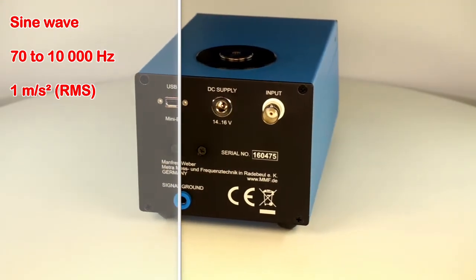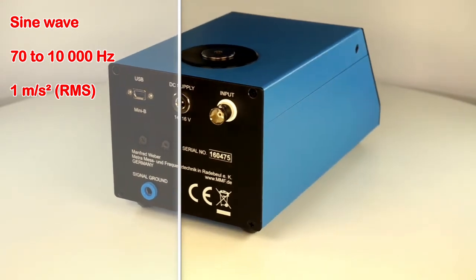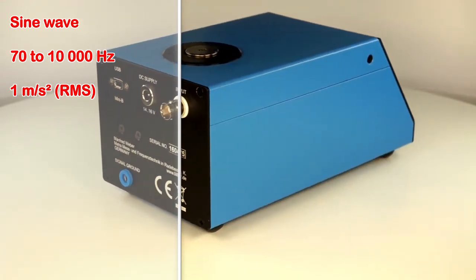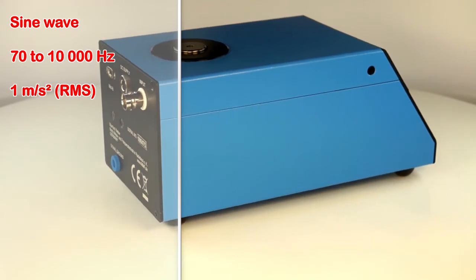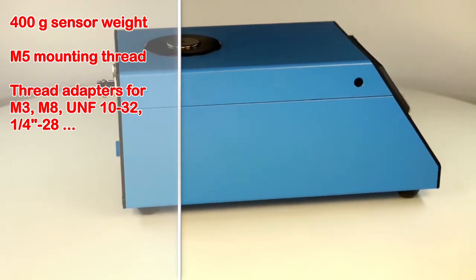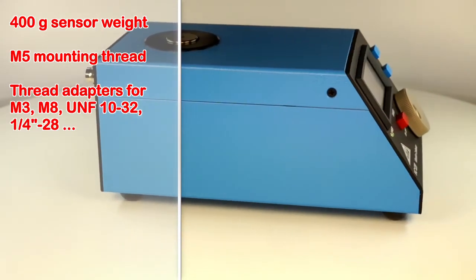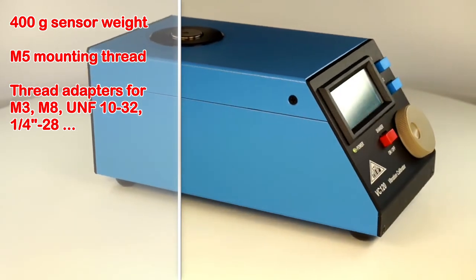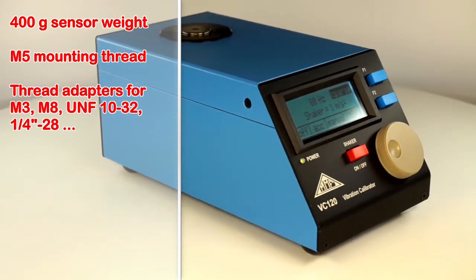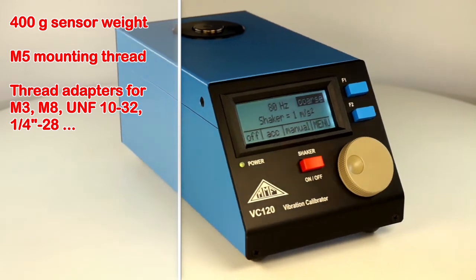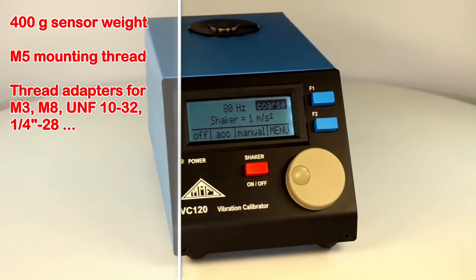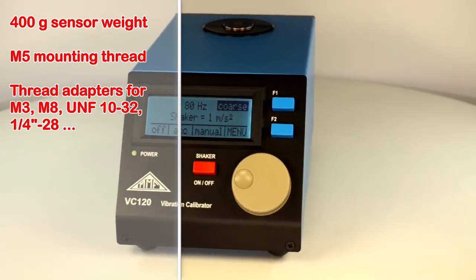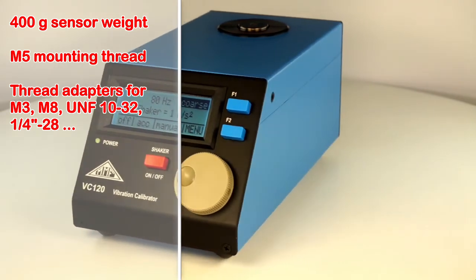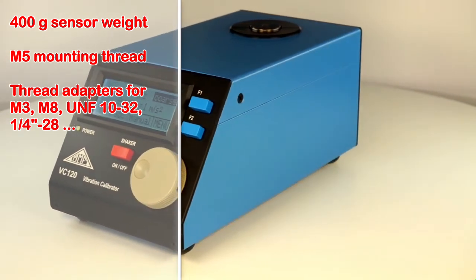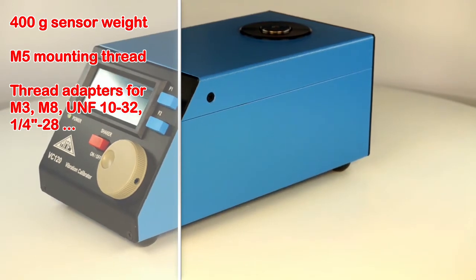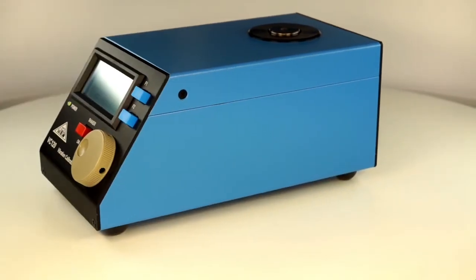It produces sine wave vibrations in the range of 70 to 10,000 Hz at a constant amplitude of 1 meter per second squared RMS. The test object can weigh up to a maximum of 400 grams. This means that you can calibrate lighter sensors as well as heavier industrial types, or high sensitivity sensors. The instrument has an M5 screw thread for attaching the sensor. Additionally, a selection of thread adapters are included as standard accessories.